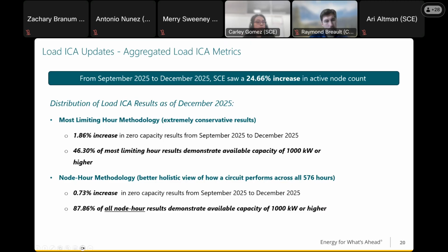Overall, the majority of SCE's results demonstrate 1,000 kilowatts or more of available capacity when referencing ICA. As you can see here in the node hour methodology, 87.86% of our active ICA nodes show 1,000 kilowatts or higher of available capacity. So looking at the system holistically, for all ICA active circuits, nearly 90% demonstrate 1,000 kilowatts or more of available capacity at the nodal level. We can go to the next slide there.